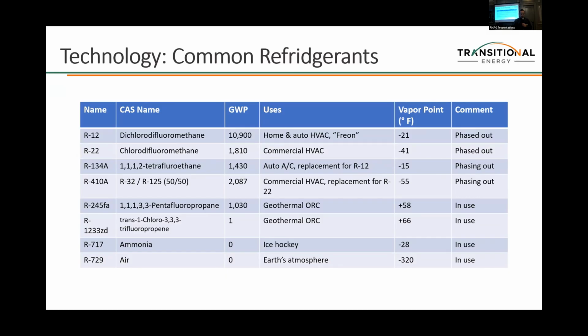Here's the global warming potential: the good old R12 and R22 from back in the day were again 10,900. Now we're at 1,000, and a lot of Europe is moving to R1233ZD, as they call it, which has a global warming potential of 1 and essentially the same properties. So this is modern refrigerants working for you.